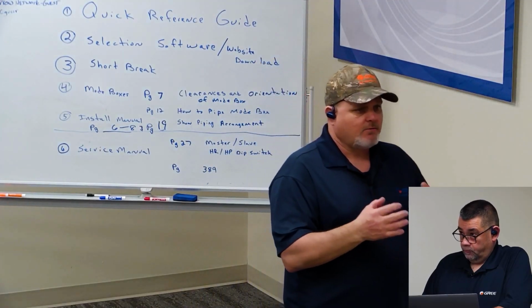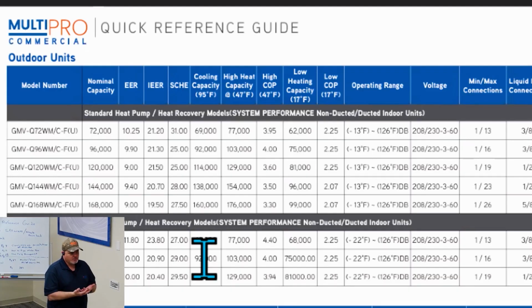Heat pump is going to be installed very much like a MultiPRO single-phase system, where we're going to use Y branches or a header, and our wiring is just going to daisy chain. But in that application, you're only going to have 2 pipes coming from the outdoor unit, and we will branch off of, like I said, a Y branch or a header and pick up however many indoor units we're using. But the downfall to that is it's still a heat pump, so all of those units have to be in heat, or all those units have to be in cool, and you're going to have a master indoor unit. When it comes to heat recovery, you no longer have to have a master, because one unit can be heating, one unit can be cooling, and it's because it's a 3-pipe situation, and your mode box is going to allow your refrigerant flow to be able to transfer heat from one room to another room and stuff like that. Yep.